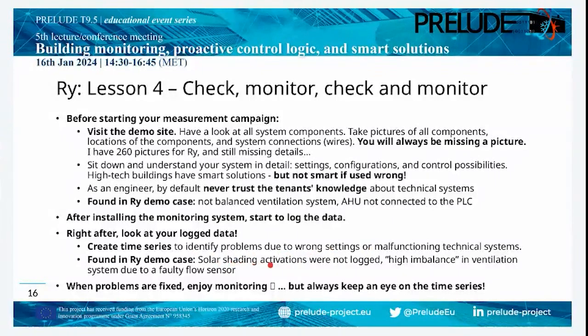We found out that the solar shading activation was not logged, and we had what we thought was a high imbalance in the ventilation system, but that was due to faulty flow sensors. So you can be misled if you're not checking these things. When problems are fixed, enjoy the monitoring, but always keep an eye on these time series, because problems will occur in the process.